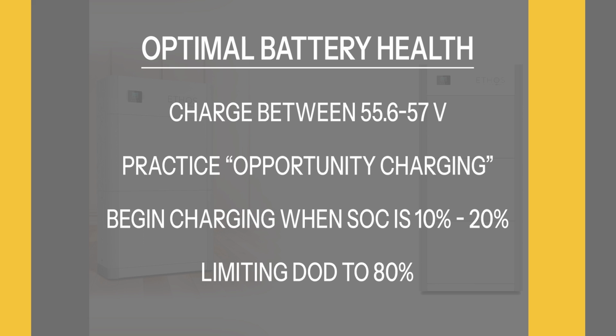While deep discharging doesn't negatively affect the battery's health, the battery management system needs a certain level of voltage to operate effectively. When it comes to discharging, even though the battery is capable of being fully discharged while maintaining constant power, limiting discharge to 80% depth of discharge can significantly extend the battery's lifespan, allowing for more than 6,000 cycles.